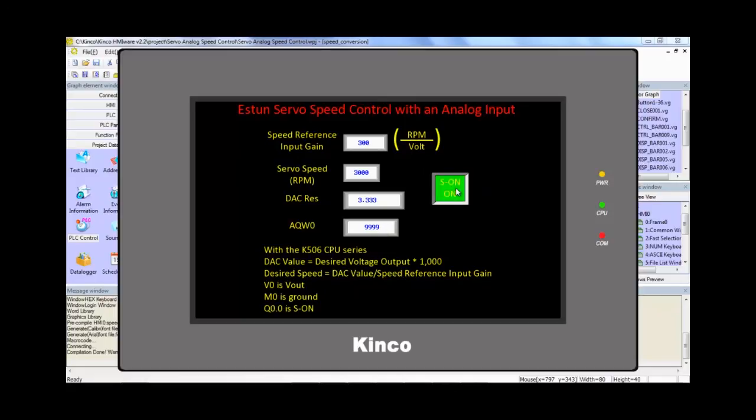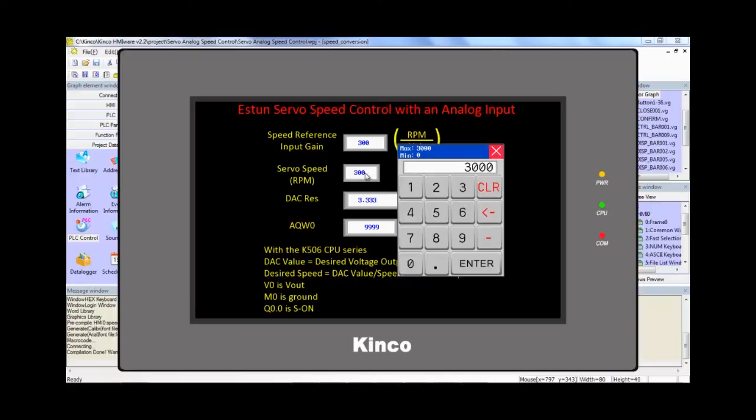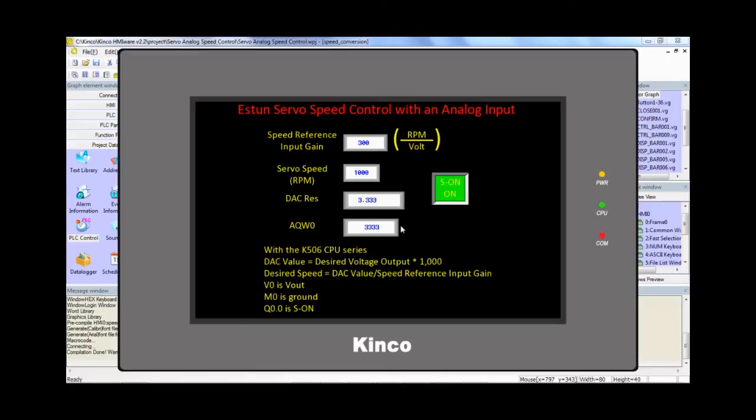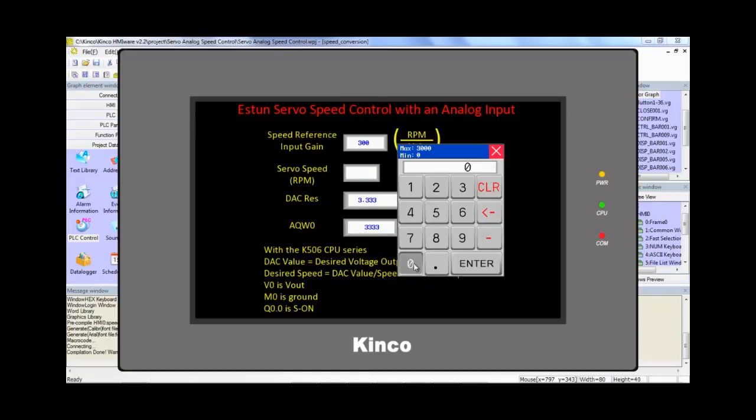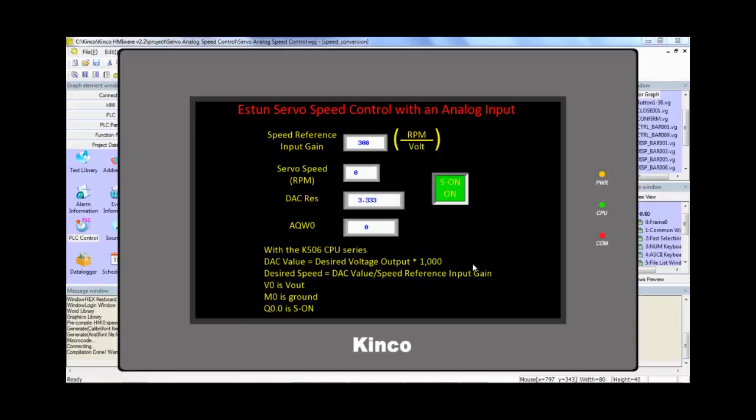Perfect. Now we're running at 3000 RPM and if we were to change this to 1000 RPM, you would see this value change and our motor is now running at 1000 RPM. If we wanted to come to a complete halt, all we do is go here, zero, enter, or we just turn the servo drive off. Either or, we'll bring it to a complete halt.